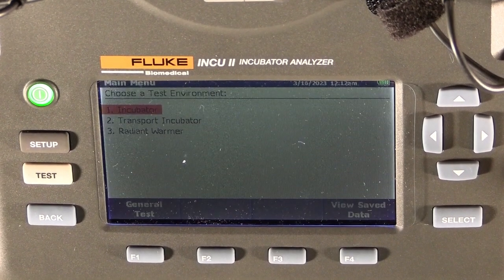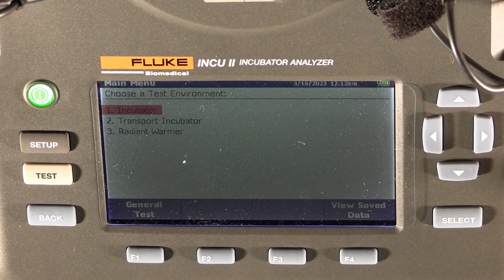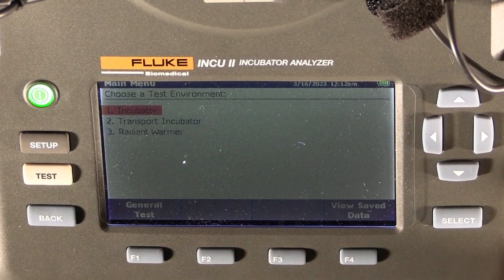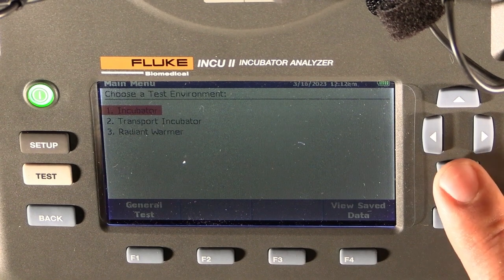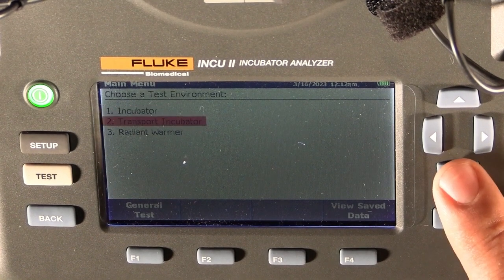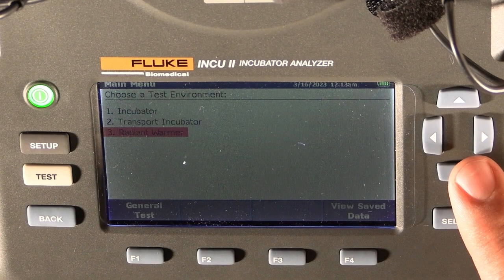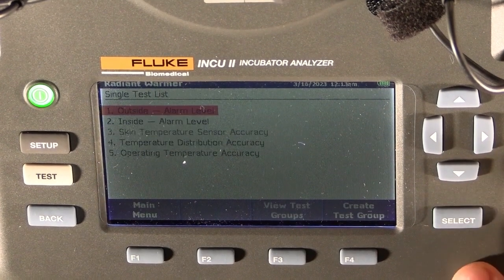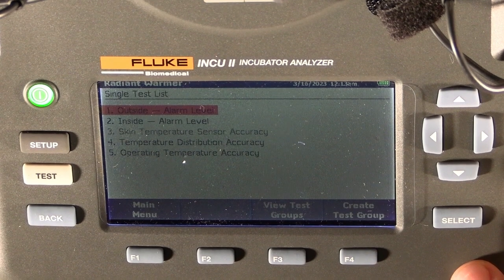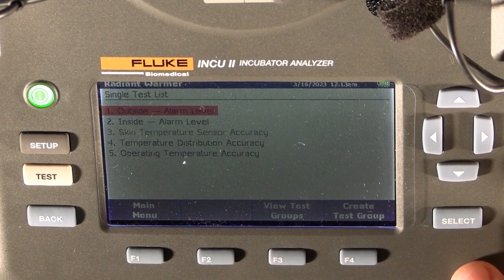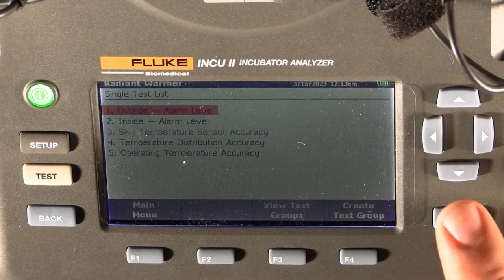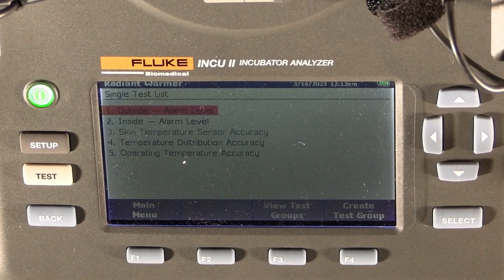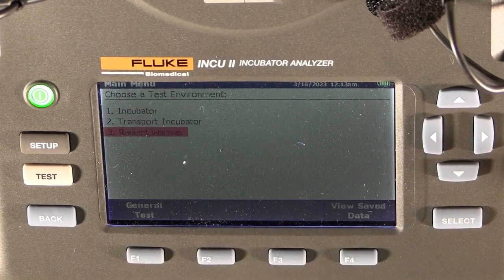And then immediately it goes to the selection menu where I can choose what it is that I'm going to test. Is it a normal incubator? Is it a transport incubator or a radiant warmer? In order to select, I'll be using the up-down arrows. Go down to transport, radiant warmer, and if you find the one you're looking for, you press the select button. Once you press select, the menu comes up inside that test schedule. The first one being the outside temperature, inside, and so forth. Now I'm just going to return back to the start again.